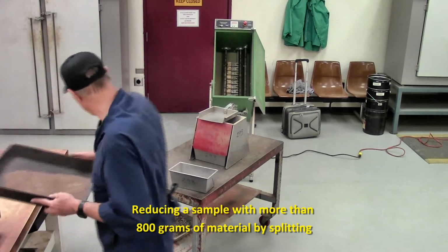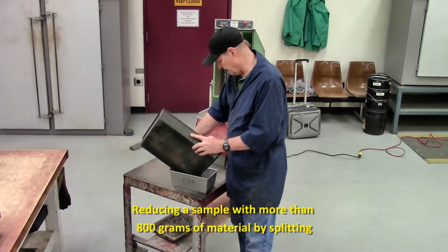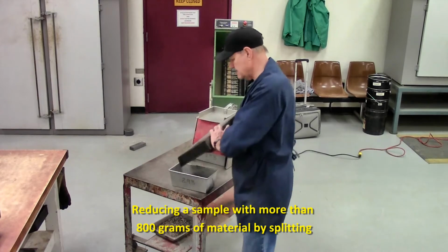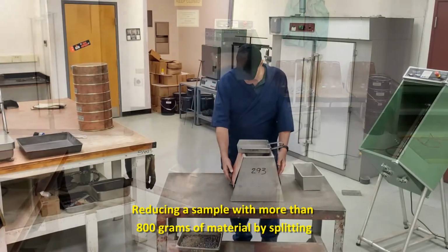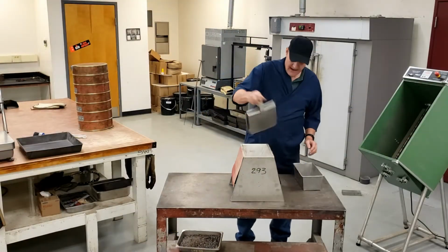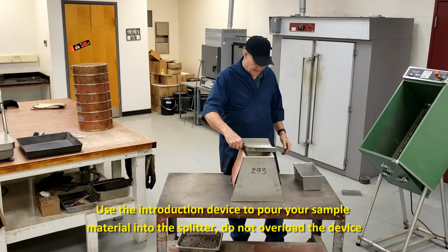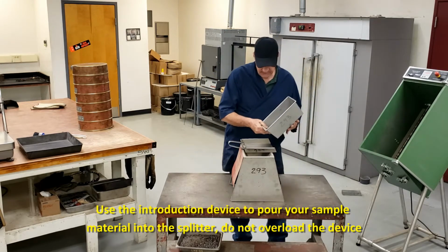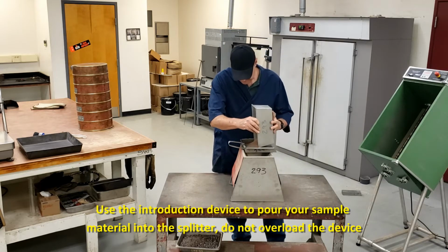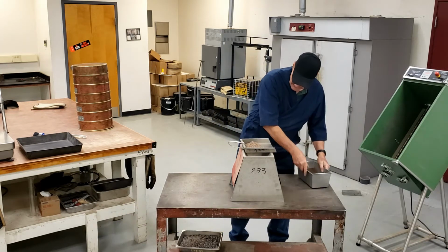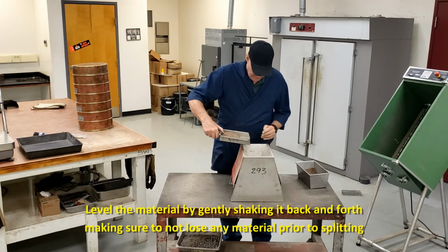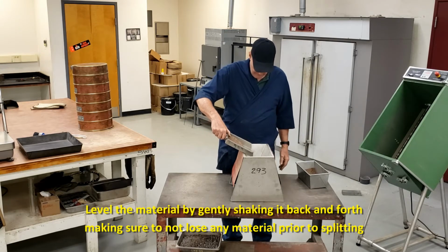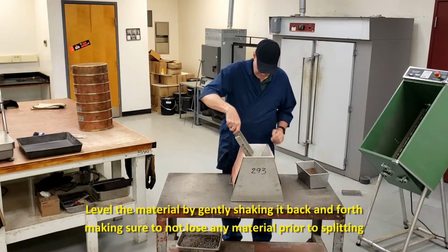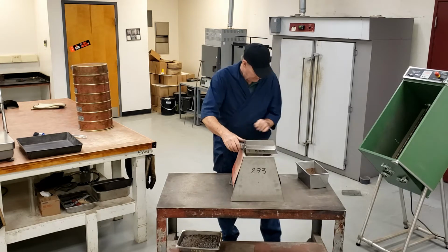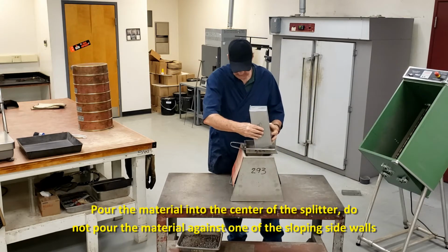Okay, now I'm going to demonstrate the splitting. If you had more than 800 grams, you would have to split it. So I have a sample here that is more than 800 grams. Make sure the pans are underneath the chutes. We have to use this introduction device in order to introduce the sample into the splitter. This part of it in there. Level it off. Pour it through the center part of the splitter. Keep doing that until you split the entire amount.